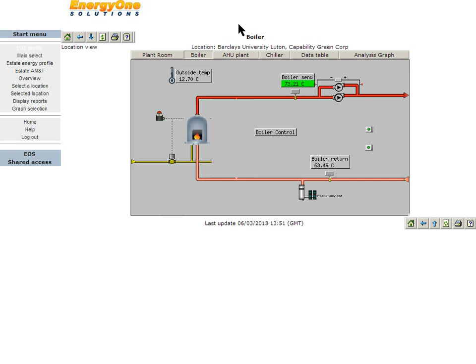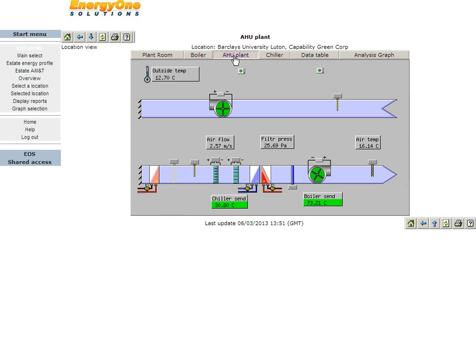This illustration shows the main constituents of the air handling system. The airflow speed of around 2.5 meters per second and the filter pressure show the airflow to be within acceptable limits. The flow temperatures of chilled water and boiler output can be seen, an assessment made to ensure against valve let-by at each matrix. Fan activity is monitored, internal and external temperatures observed, and a free cooling assessment made.